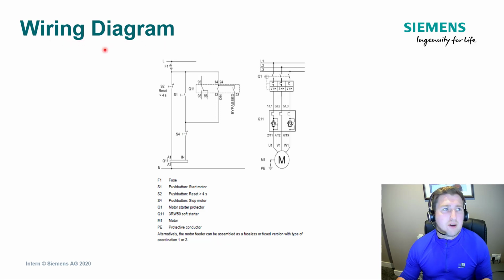In here we have a wiring diagram also, so the wiring diagram goes into the specifics of how you typically connect a device up. So this shows you the main circuit. On the main circuit we've got a 3RV motor starter protector, we've got a soft starter, and then we've got the motor, and that's a typical configuration for a type 1 layout. If you had type 2 perhaps, you might have two forms of fusing in here. So the difference between type 1 and type 2 is that if you use type 1, if you have a short circuit, this device, the soft starter, might have to be replaced.